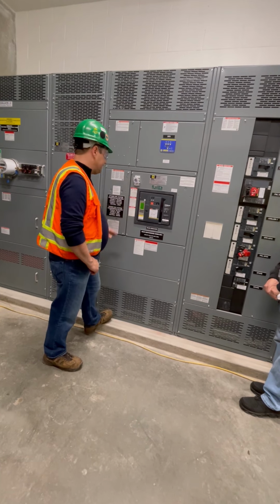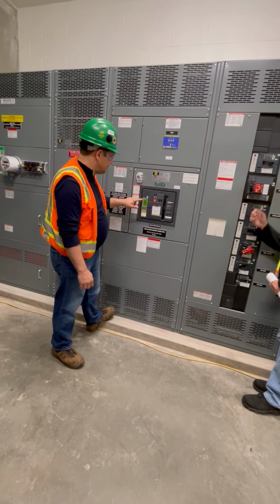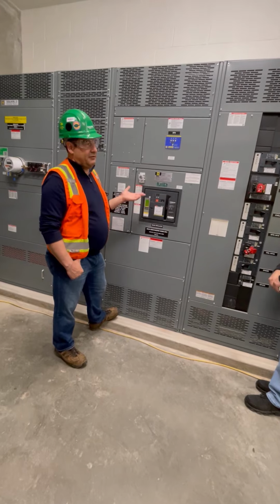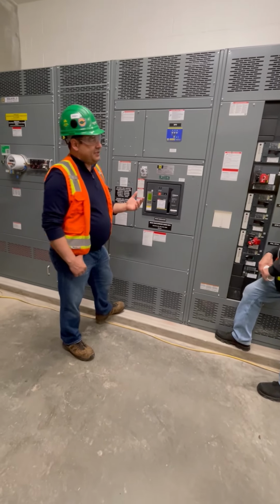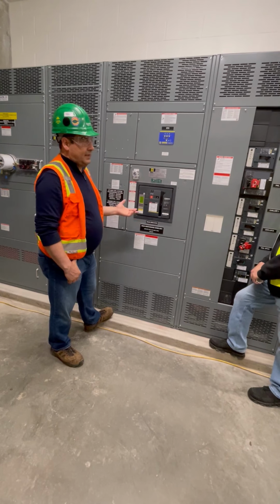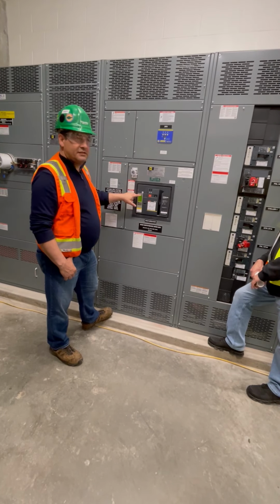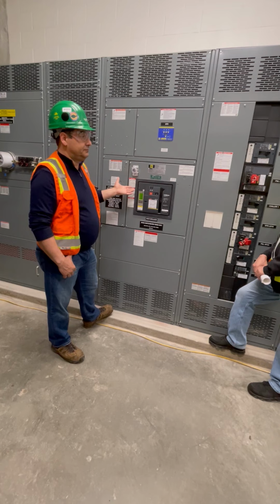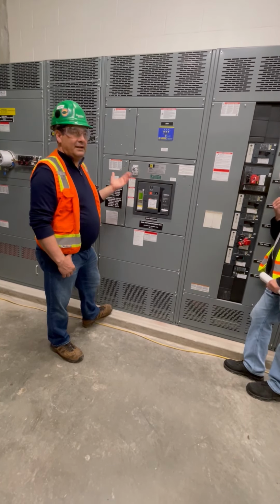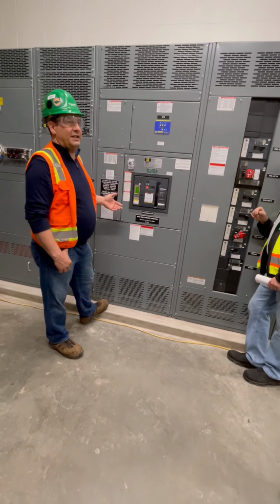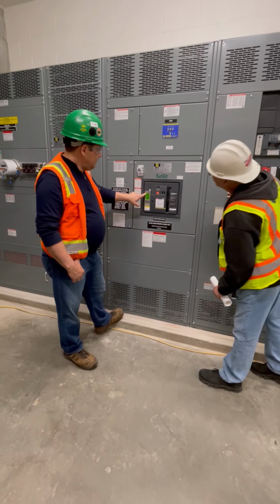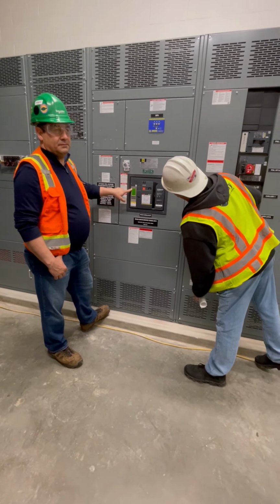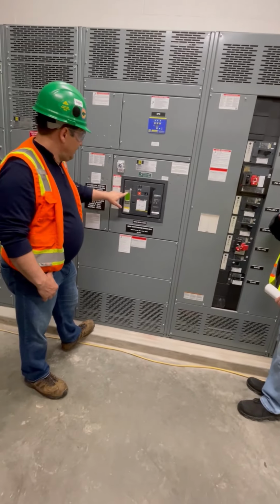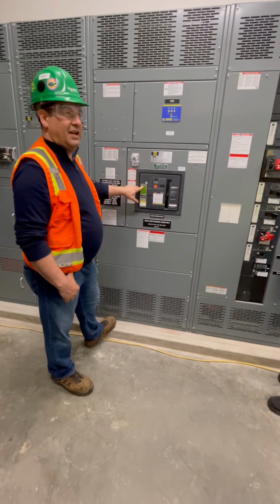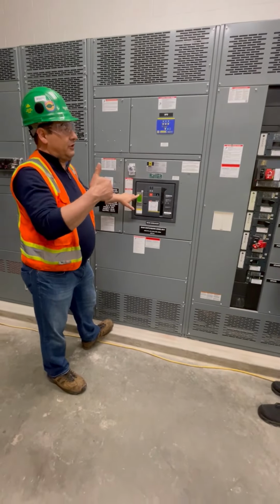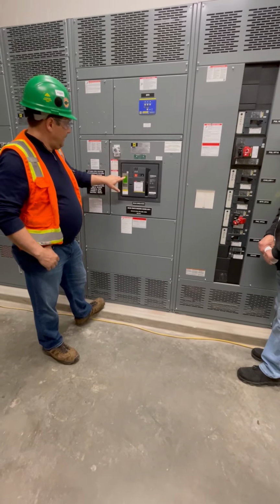Now, if this breaker ever trips, one of these LEDs will come on. And this is why it's very important you remember this, because if you call Schneider to help you diagnose the issue, this is one of the first things I'll ask you: what did it trip on? If you reset the breaker, then the LED goes away and we'll have to wait for the next event. But this right here tells you that you tripped on long time, overload. This right here is short time or instantaneous. You had a spike of current in there, right? Ground fault.